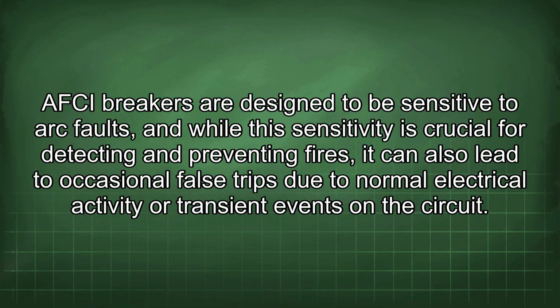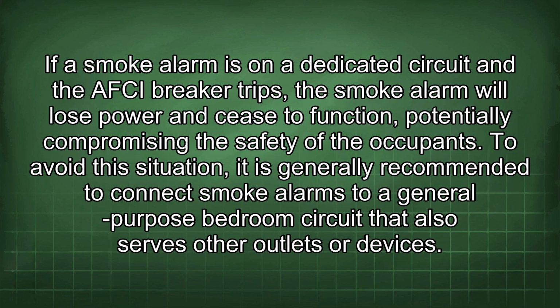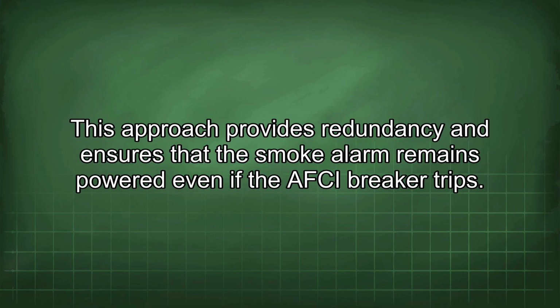AFCI breakers are designed to be sensitive to arc faults, and while this sensitivity is crucial for detecting and preventing fires, it can also lead to occasional false trips due to normal electrical activity or transient events in the circuit. If a smoke alarm is on a dedicated circuit and the AFCI breaker trips, the smoke alarm will lose power and cease to function, potentially compromising the safety of the occupants. To avoid this situation, it is generally recommended to connect smoke alarms to a general-purpose bedroom circuit that also serves other outlets or devices. This approach provides redundancy and ensures that the smoke alarm remains powered even if the AFCI breaker trips.